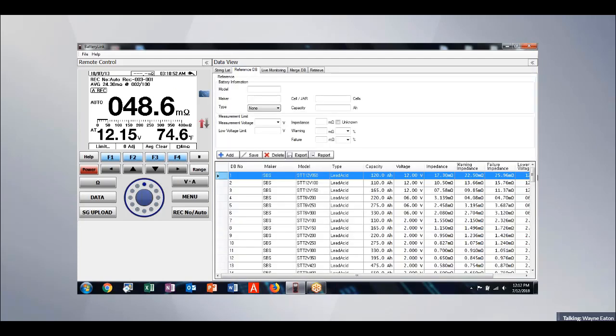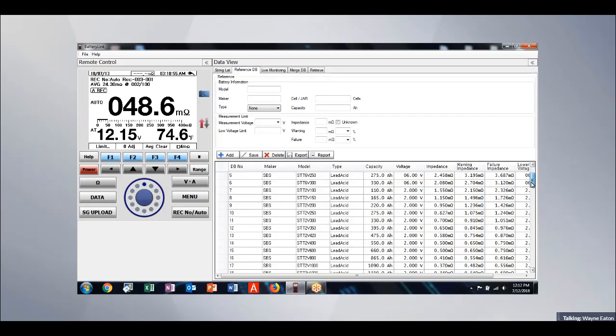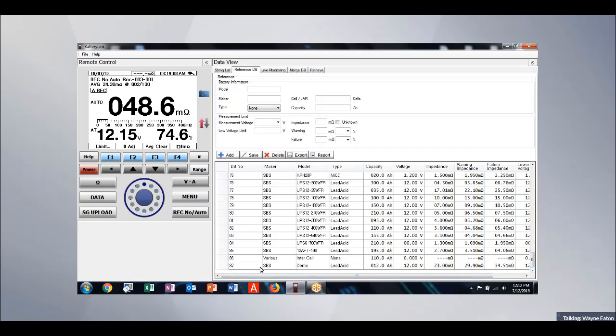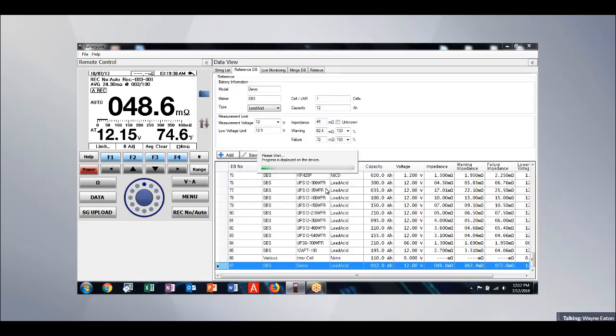So we're going to get out of this quick start guide, and we're going to go over the actual software. The first thing we've got is a reference database, and this is a list of all of the possible battery model numbers that we have at our different installed locations, and then all the reference values that go along with those. We're going to come down here to the very bottom. We're at 87 SBS demo, 12 amp hour lead acid, impedance 23 milliohms. This is the reference value we're going to use for the demo today. And I just took a measurement on this battery, and its impedance is actually up around 48. So let's modify that. We'll hit save. And it's going to update that data onto the unit.